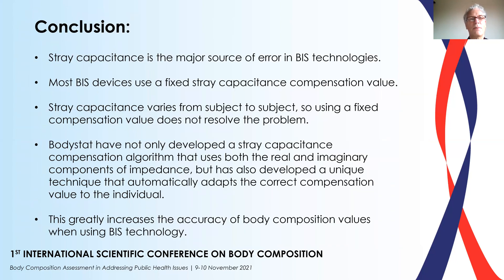In conclusion, stray capacitance is the major source of error in BIS technologies, and it's introduced by the patient's body itself, varying from subject to subject. A fixed stray capacitance does not resolve the problem and can actually make it worse. All BIS devices use a fixed stray capacitance — except for the Bodystat one. Bodystat has not only developed a stray compensation algorithm that uses both the real and imaginary components of impedance, but has also developed a unique technique that automatically adapts the correct compensation value to the individual. This greatly increases the accuracy of body composition values when using BIS technology, which is very important for clinical work and for ensuring repeatability and accuracy within your trials. Thank you.